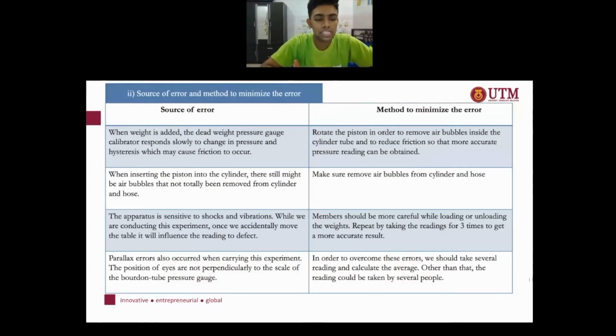The second question, they ask us the source of error and method to minimize the error. So the source of error, the first one, when weight is added, the dead weight pressure gauge calibrator responds slowly to change in pressure and hysteresis, which may cause friction to occur. So the method to minimize this error, we rotate the piston in order to remove the air bubble inside the cylinder tube and to reduce friction so that a more accurate pressure reading can be obtained.